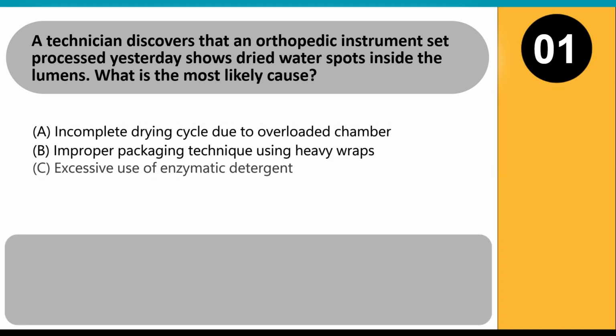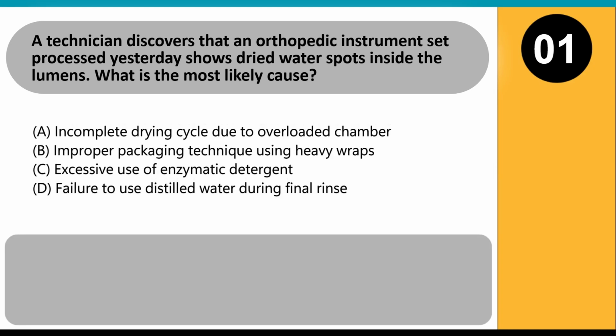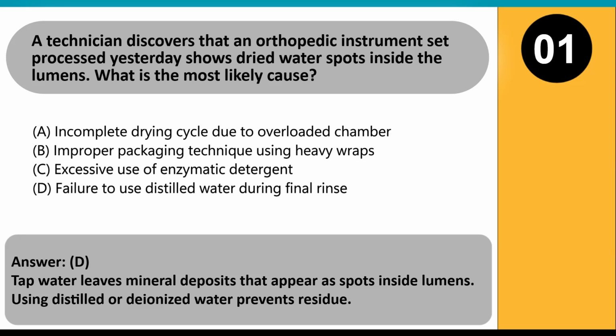A technician discovers that an orthopedic instrument set processed yesterday shows dried water spots inside the lumens. What is the most likely cause? A. Incomplete drying cycle due to overloaded chamber. B. Improper packaging technique using heavy wraps. C. Excessive use of enzymatic detergent. D. Failure to use distilled water during final rinse. Answer: D. Tap water leaves mineral deposits that appear as spots inside lumens. Using distilled or deionized water prevents residue.